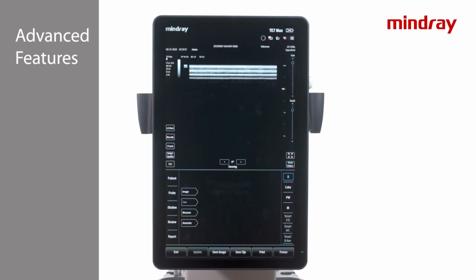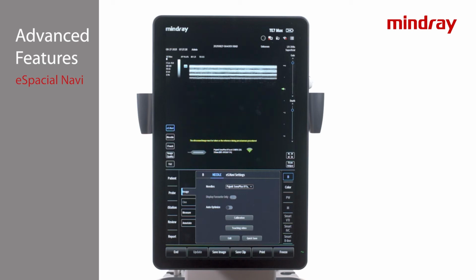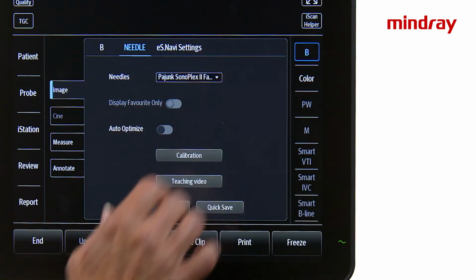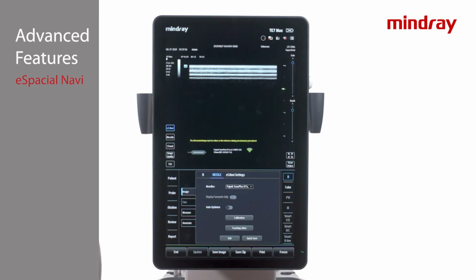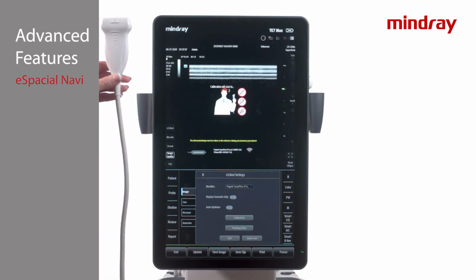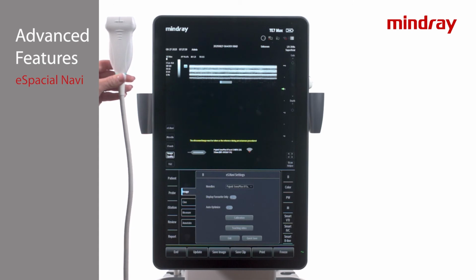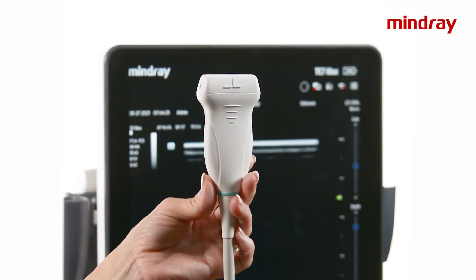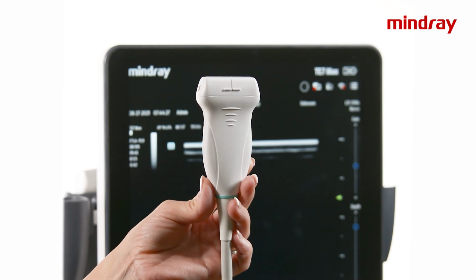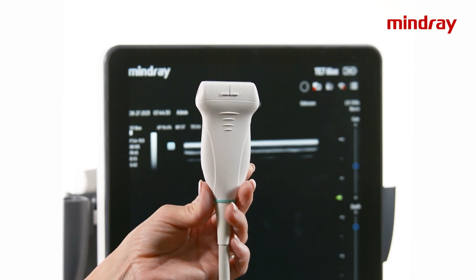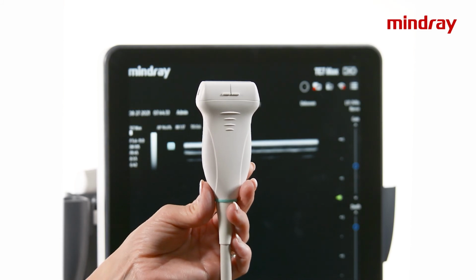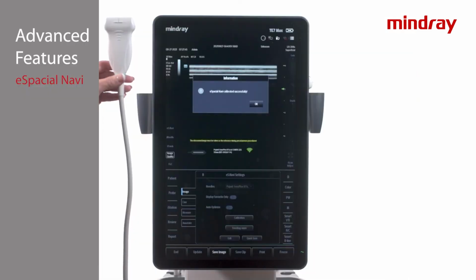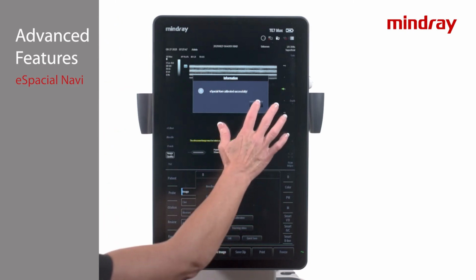Initiate the L11-3 VNS or L12-3 VNS transducer in preferred exam mode. Press the eSpacial Navi tab on the left of the monitor to activate. Verify the needle being used is from the approved list in the Image tab. Press the Calibration button with the transducer approximately 12 inches from the system at the same level as the top of the TE7 monitor. Make sure the transducer indicator notch is toward the left of the screen during calibration. The notch correlates to the M on the imaging screen. A message will appear when complete.